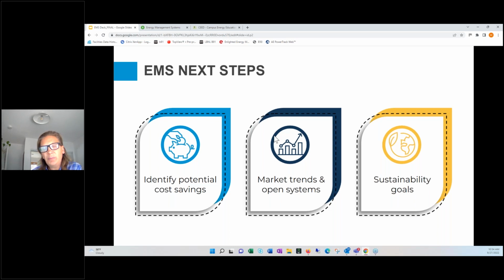So an example of that would be, I'm going to go out and look at the weather data, and let's say Thursday it's going to be really hot out. So what the AI or computer learning would do is then say, I'm going to go change my set points off my air handler or wherever, maybe in the zones. And then I see that the weather on Friday dramatically goes back to being cooler outside, or the high is 20 degrees less than it was the previous day. So then it'll go change the set points again, proactively, so that we make sure we do save energy. It should help with comfort as well, but ultimately, again, trying to be proactive instead of responsive. So that's where they're trying to go, or one of the things that they're working on.